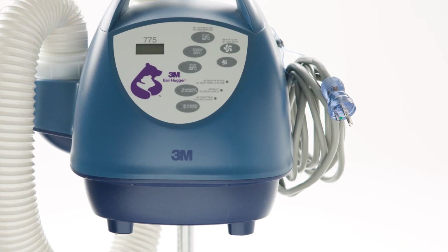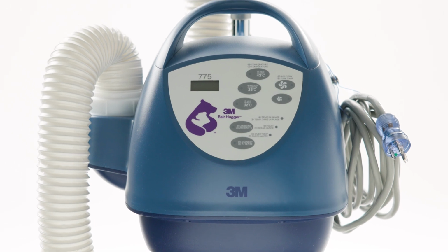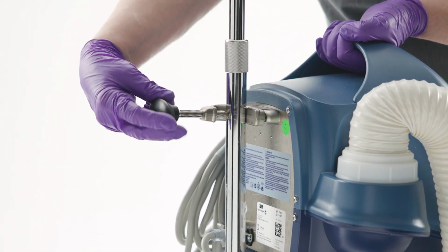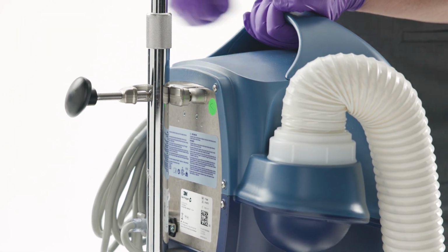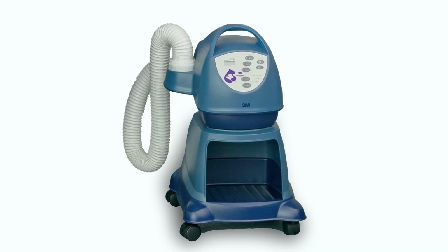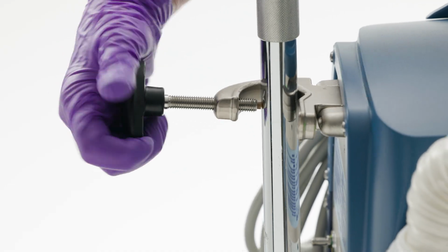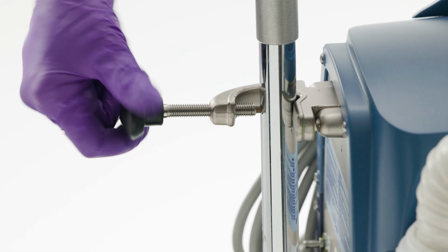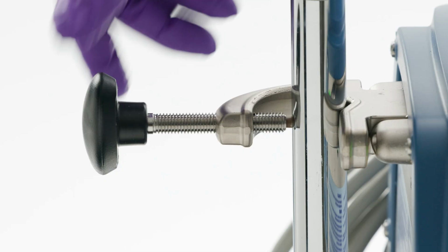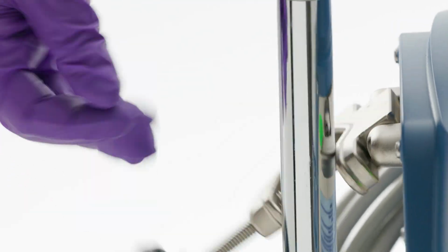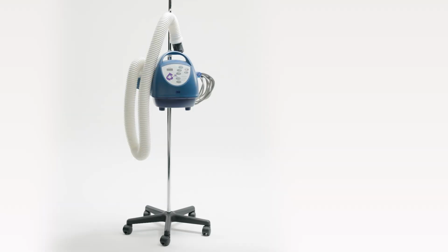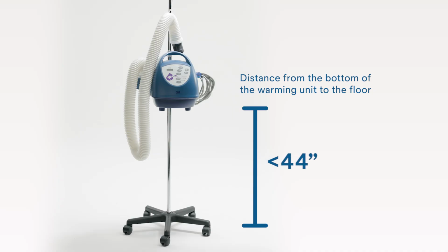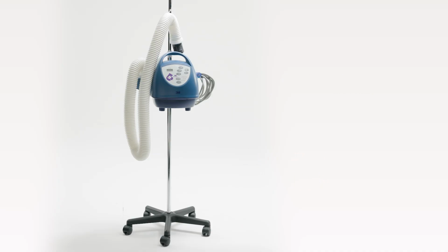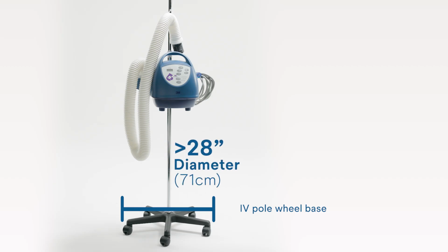The 3M Bair Hugger Warming Unit Model 775 should be placed on a flat, hard, dry surface or mounted on an IV pole or rolling cart. To mount the warming unit to an IV pole, turn the clamp handle clockwise to tighten the clamp on the IV pole and counterclockwise to release. To prevent tipping, the distance from the bottom of the warming unit to the floor must be less than 44 inches, 112 centimeters, and the IV pole wheelbase must be at least 28 inches, 71 centimeters in diameter.